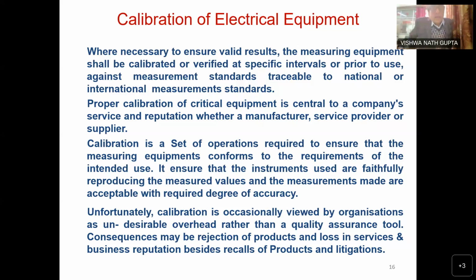Sir, this is as good as mandatory. Before reporting our results, our test equipment should be calibrated by a proper calibration agency, and this should be traceable to national and international standards. What I mean to say, sir, is that if in the USA they want some product at a very, very high standard, giving the technical specification, that is their requirement. It goes from the SI to their national standard. And if India is going to manufacture it, we should test and report in a way that is traceable and the same. Then it will be acceptable to their technical specification. So that is why calibration of electrical equipment is required.